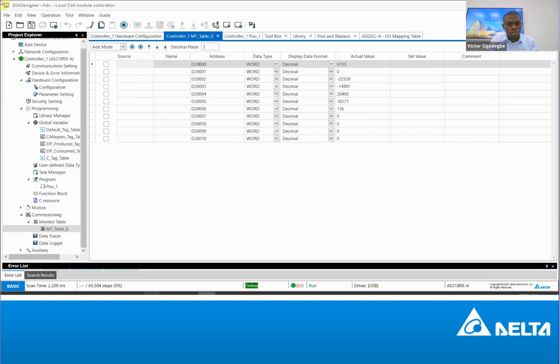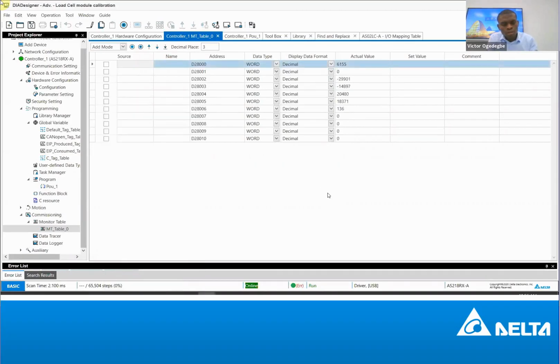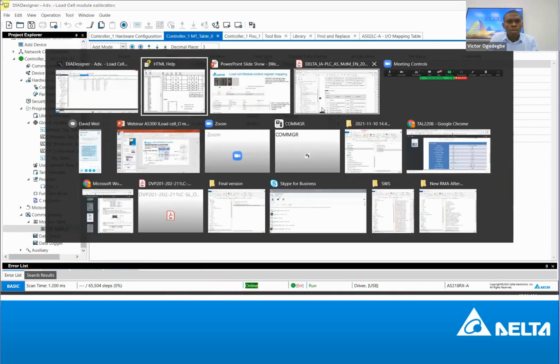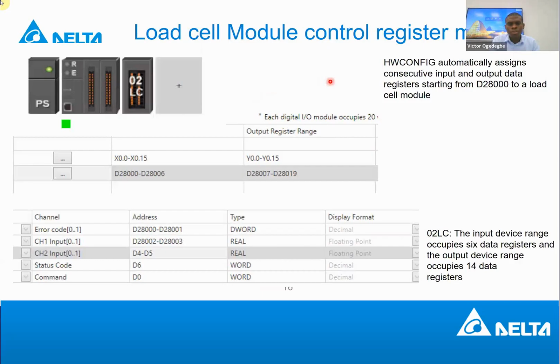Now let's go to our presentation, then we'll wrap up with some short configuration. Now we're going to look at some functions in the PLC. This is what I was showing you: the address is mapped. Another thing on this very address, for example, this command here is D0. Anything you write on D0 automatically goes to the command register and is executed. It's the same thing that the TO instruction would also do.